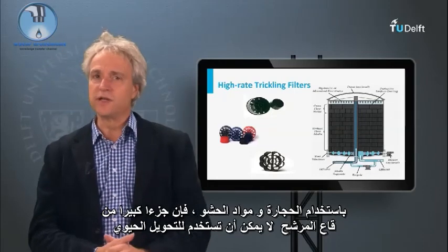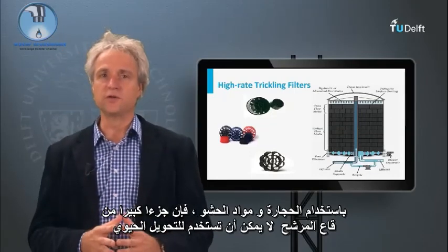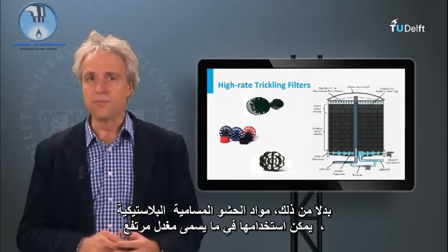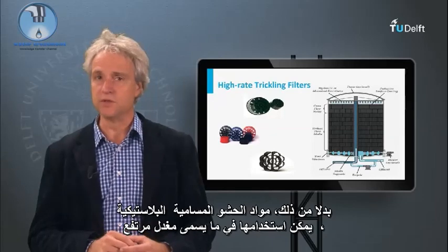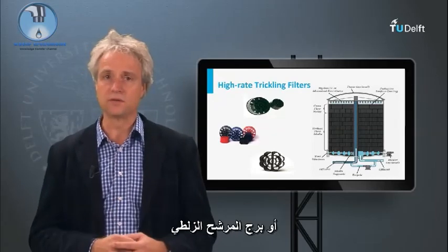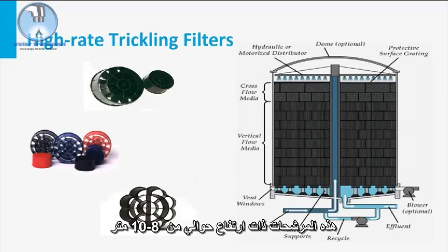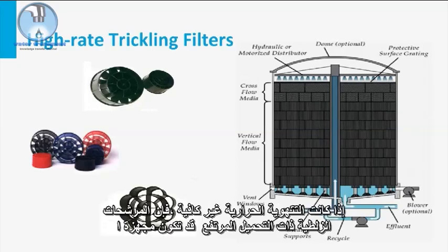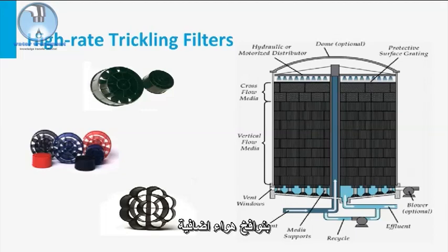By using stones as filling material, a large part of the filter bed cannot be used for bioconversion. Alternatively, very porous plastic packing material can be used in the so-called high-rate or tower trickling filter. These filters have a height of about 8 to 10 meters. Since the bioconversion rate is much higher, oxygen supply is much more critical in these filters. If convective aeration is non-sufficient, high-rate trickling filters might be equipped with additional blowers.